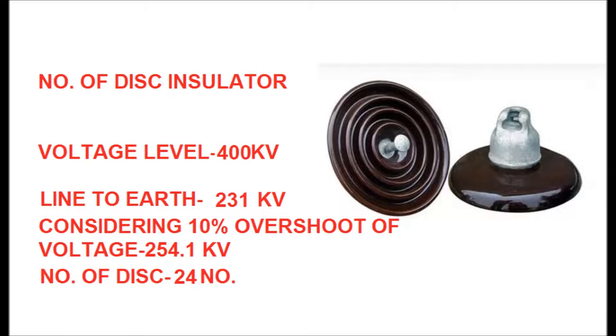For the 400 kV system, the line-to-line voltage is 400 kV. The line-to-earth voltage is 400 divided by √3, equal to 231 kV. Considering 10% overvoltage: 231 × 1.1 = 254.1 kV. Dividing 254.1 by 11 gives approximately 23. Adding 1 for safety gives 24 discs for suspension type string and 25 discs for tension type string in a 400 kV system.